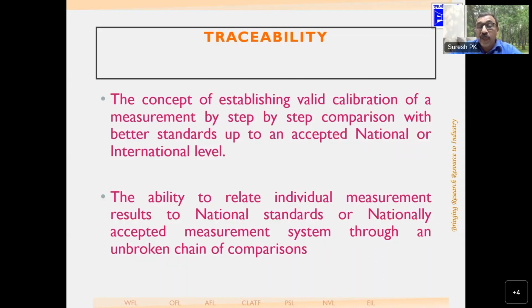Then you have to maintain the calibration records. Records are also important. You have to maintain the calibration records with an accepted measurement system. The accepted measurement system in this case, for you, is probably the RRSLs. You may be spending some money on that, but that is not important. I mean, spending money is not the issue; it may become critical if you don't calibrate. Your entire system may collapse if your measurements are not correct.